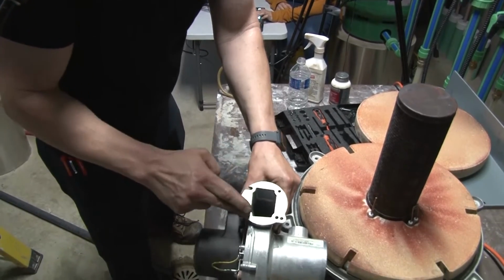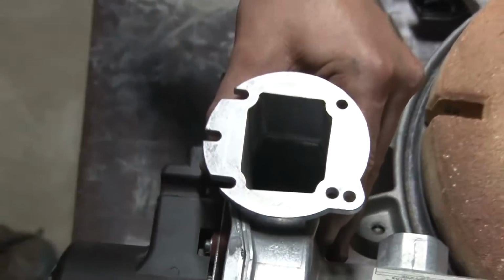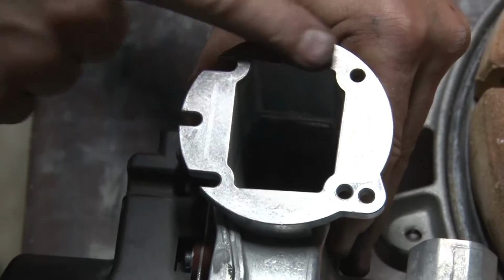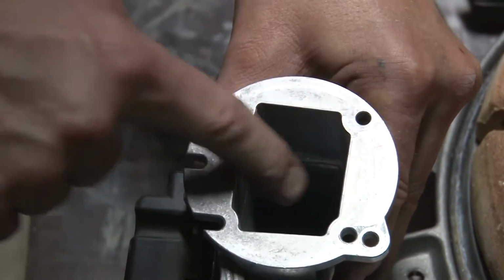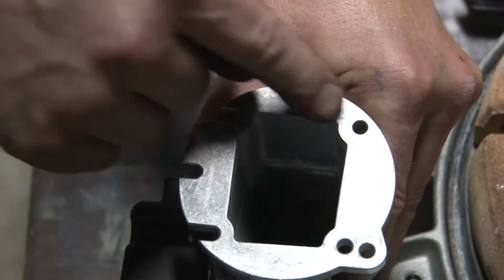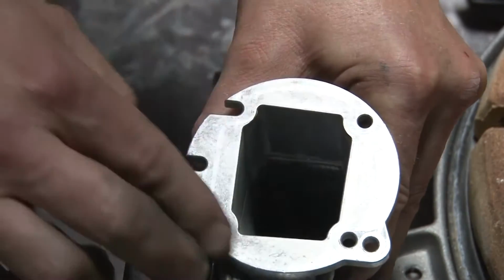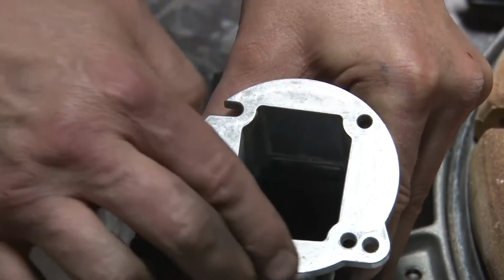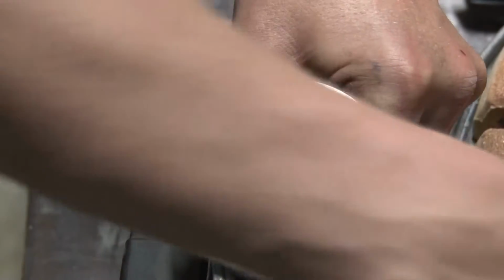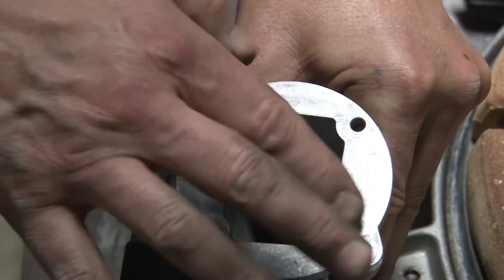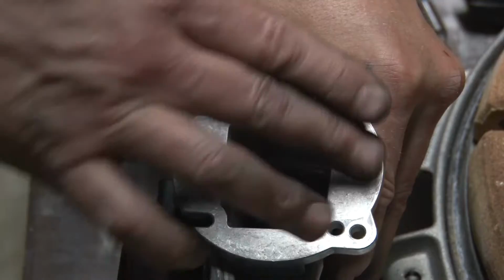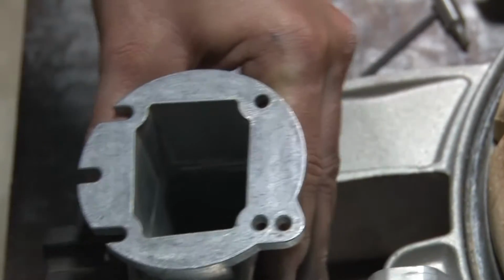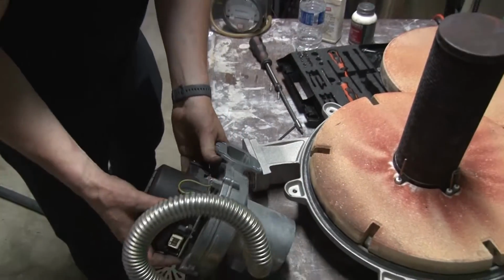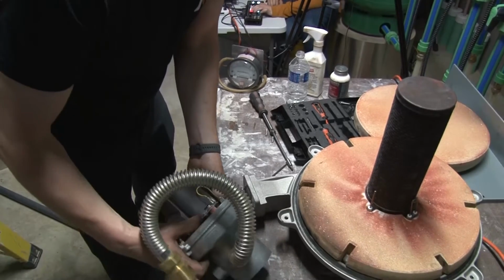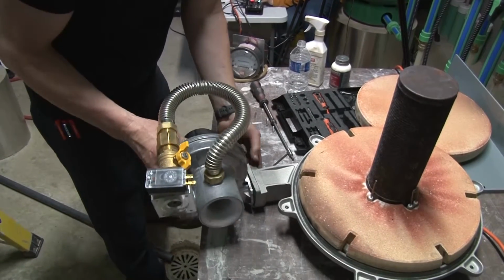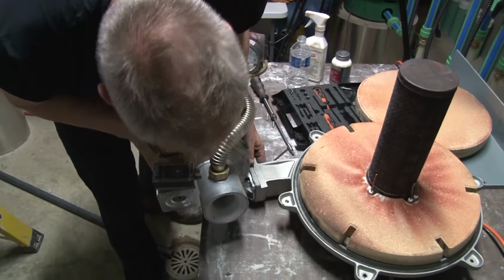This is really nice and shiny. These boilers are 6, 7, 8 years old, I think. If I saw this dirty, pitted in here, like a dark gray and pitting, that tells me we've got flue gas recirculation. So we're pulling flue gas into the venturi, and it'll stain the aluminum. This one here is really nice, like the day it was installed, basically. So I don't worry about flue gas recirculation with this particular boiler. So I got all that stuff checked. Everything looks good. I could put the burner back together here now.